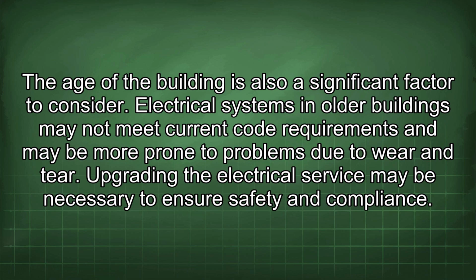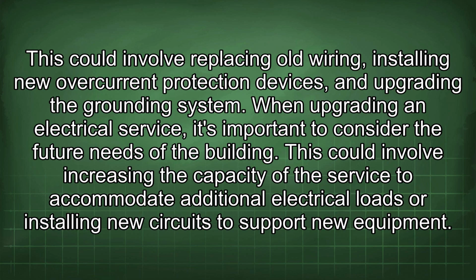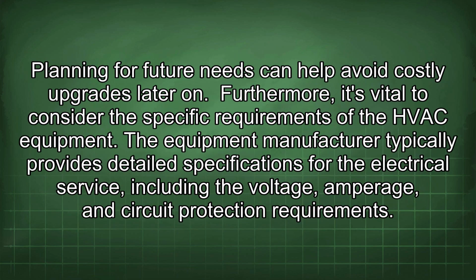The age of the building is also a significant factor to consider. Electrical systems in older buildings may not meet current code requirements and may be more prone to problems due to wear and tear. Upgrading the electrical service may be necessary to ensure safety and compliance. This could involve replacing old wiring, installing new overcurrent protection devices, and upgrading the grounding system. When upgrading an electrical service, it's important to consider the future needs of the building. This could involve increasing the capacity of the service to accommodate additional electrical loads or installing new circuits to support new equipment. Planning for future needs can help avoid costly upgrades later on.